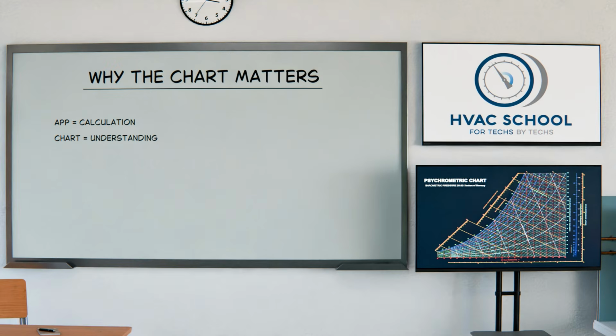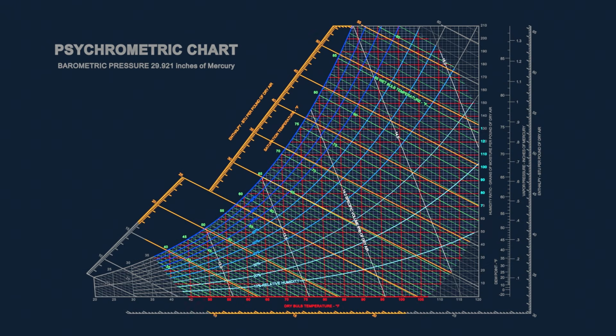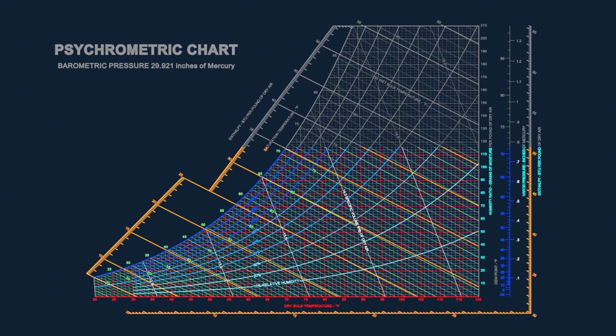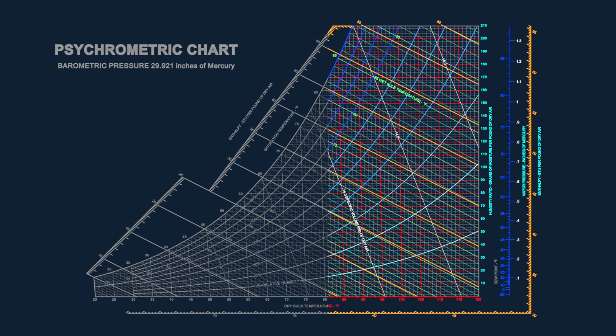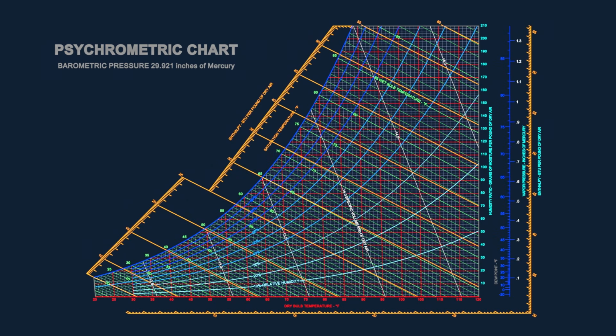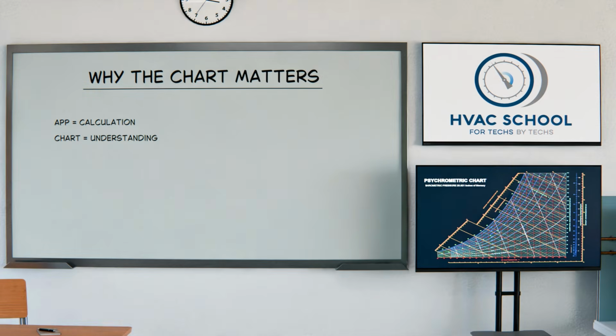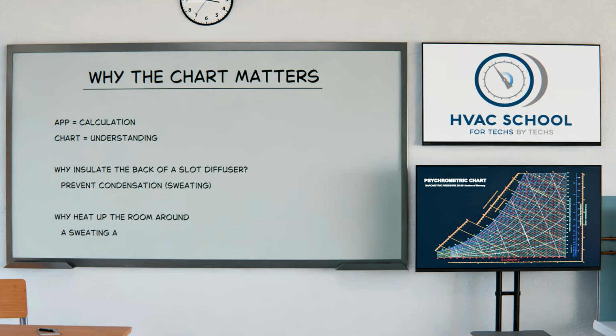But the chart helps you understand the relationships. It shows you how temperature, humidity, and heat interact. Without that, the app is just a calculator with no soul, and you don't get the connection. And often, it's the connection that helps you troubleshoot what to do about a problem. For example, do you know what insulating the back of a slot diffuser will do, or heating up the room around an air handler that's sweating? If you've never paid attention to the relationships on the psychrometric chart, then probably not.